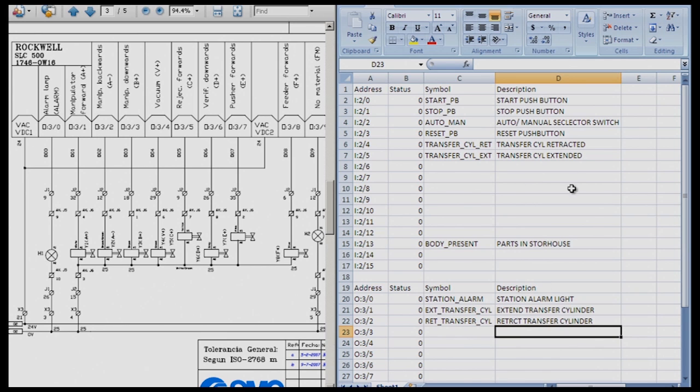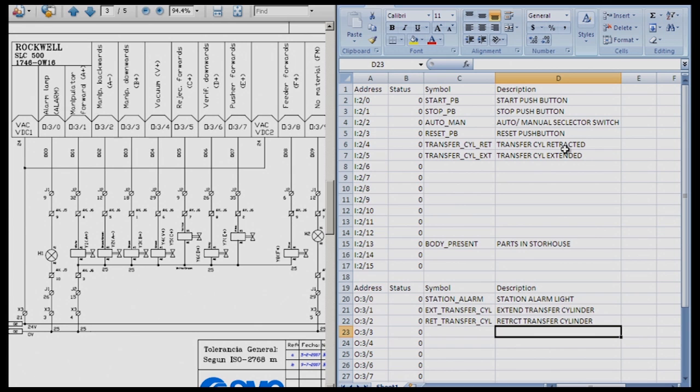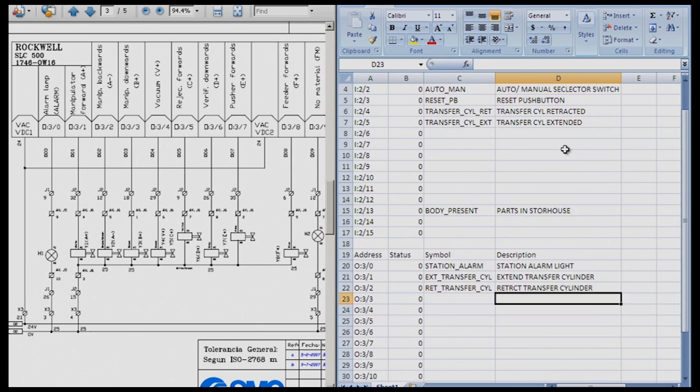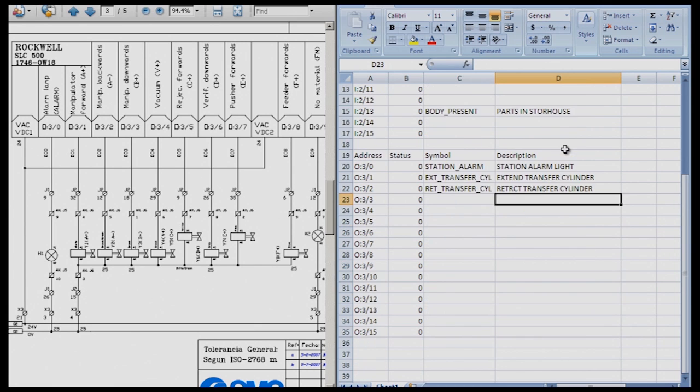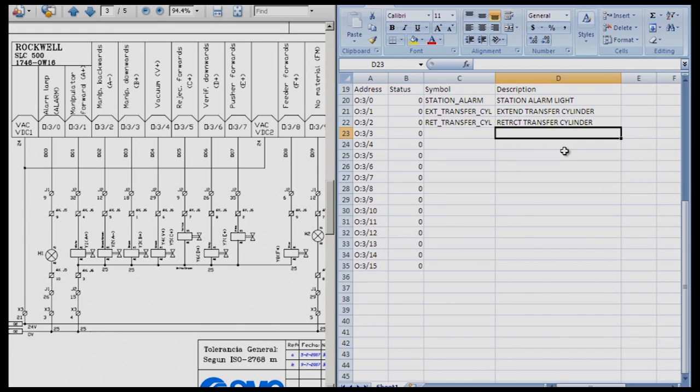There's actually a method of madness between all those verbiages. If you look at an input and you say transfer cylinder retracted, that's a state that the cylinder is actually in. So we could expect it to be retracted. If we say transfer cylinder extended, that again is a state that we can expect that cylinder to be in. So we look at the outputs then and we say extend. That is an action. So we would expect motion to occur. So we say extend transfer cylinder and retract transfer cylinder and we would expect those types of motions to occur.